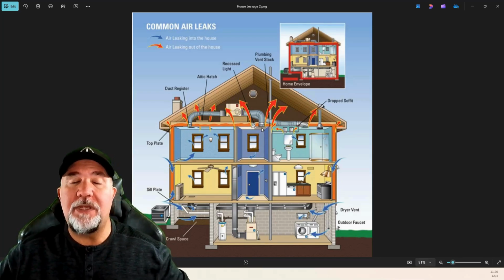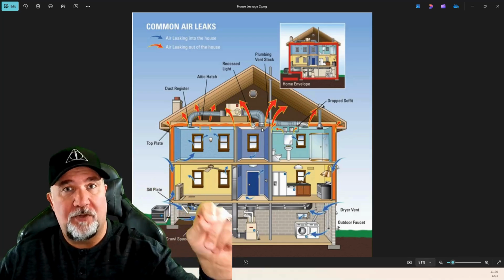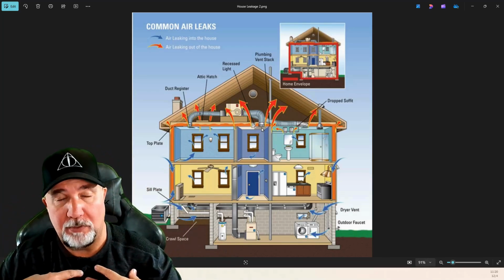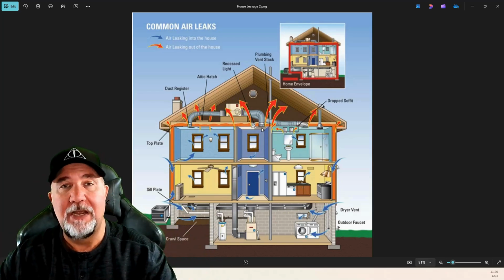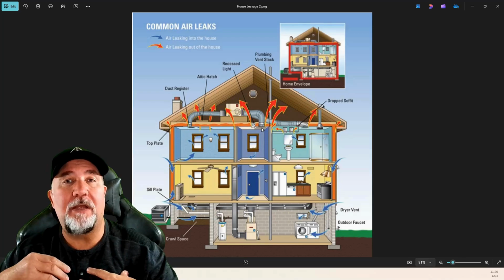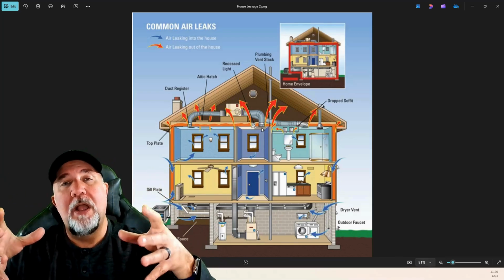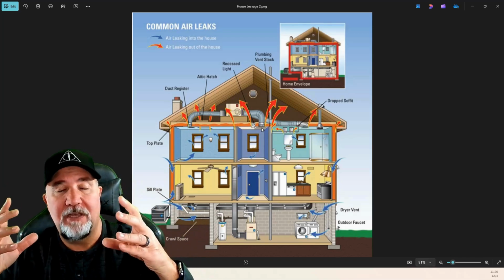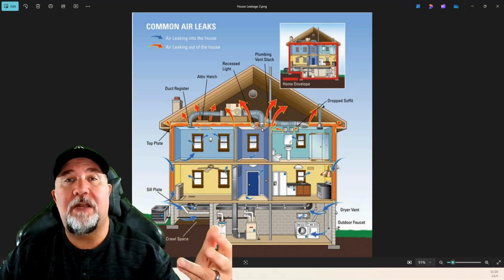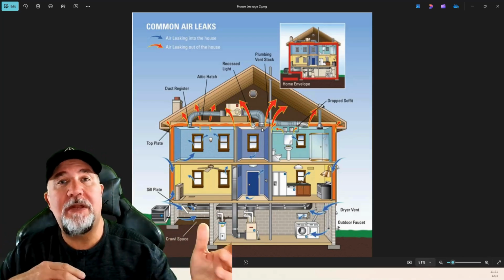And the reason being is we can then more purposefully extract air from that room, as well as purposefully put air in that room. And if you have the right balance of air, and I'm a firm believer, most people won't do this, I'm a firm believer in putting dampers in returns and supplies, because otherwise it's just a big hole, and the amount of air that gets pushed out or sucked in is going to be determined based on a lot of external things like outside air pressure, duct sizing, air fan speed, and things of that nature, which may not always be consistent.